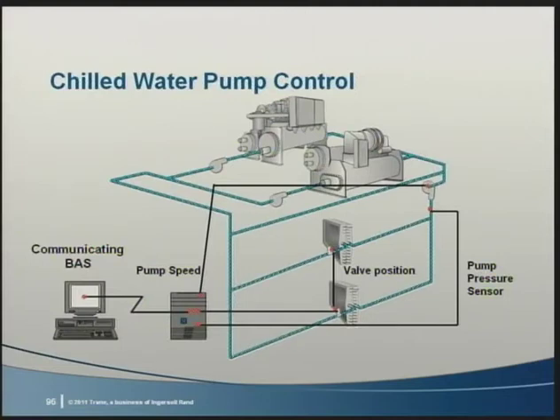Every 15 minutes or so, the automation system has the option to reset the pressure set point based on valve position. The valve position doesn't directly adjust the pump speed. It gradually has an influence on it by resetting the pump pressure set point. Referred to as pump pressure optimization or critical valve reset, this reduces system pumping power substantially. The same concept has been used on the air side for over 2 decades. With the advent of direct digital control of valves, pump pressure optimization is being used more often than in the past. Let's look at how it operates.